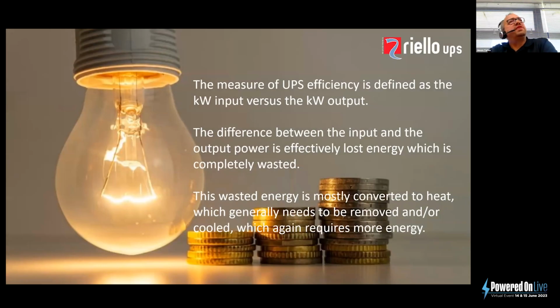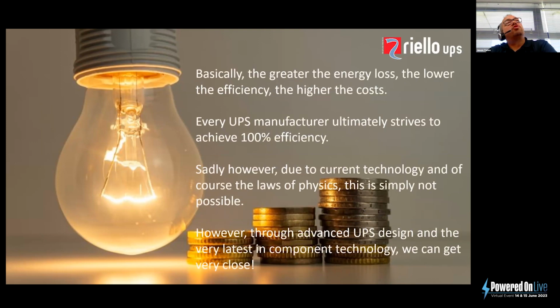The measure of any UPS's efficiency is defined as the kilowatt input versus the kilowatt output. The difference between the input and the output power is effectively lost energy, which is technically completely wasted. This wasted energy is mostly converted to heat, which generally needs to be either removed or cooled, which again requires more energy. So the greater the energy loss, the lower the efficiency and the higher the costs.